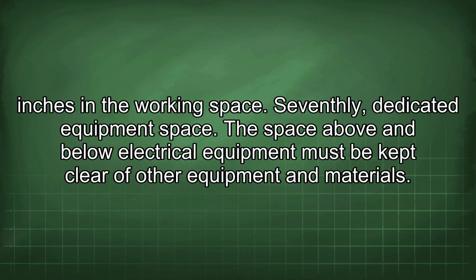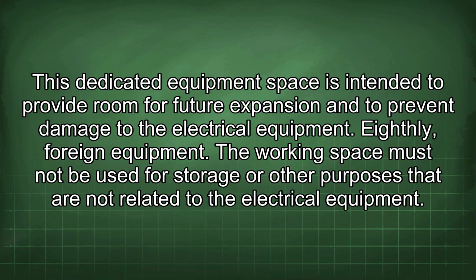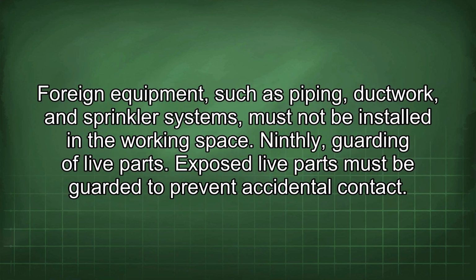Seventhly, dedicated equipment space. The space above and below electrical equipment must be kept clear of other equipment and materials. This dedicated equipment space is intended to provide room for future expansion and to prevent damage to the electrical equipment. Eighthly, foreign equipment. The working space must not be used for storage or other purposes that are not related to the electrical equipment. Foreign equipment, such as piping, ductwork, and sprinkler systems, must not be installed in the working space.